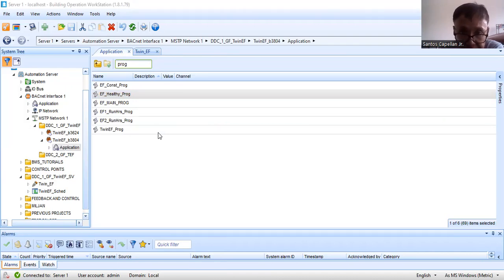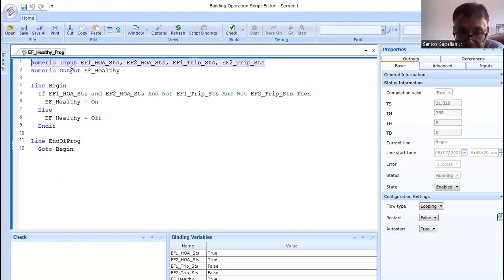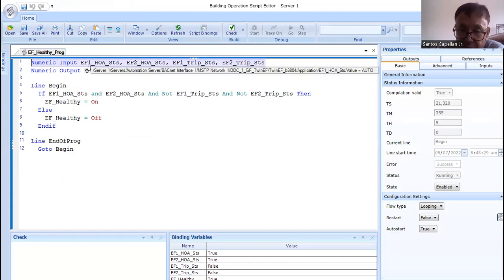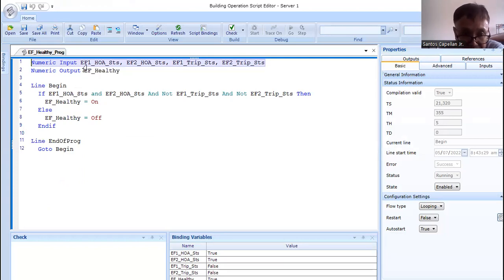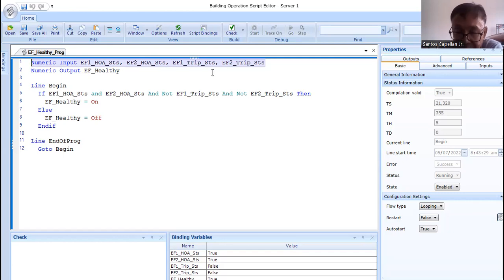I will share this screen so you can see it. This is a very small program. I have the first lines as numeric input. These numeric inputs are the points I will get from the controller. First: EF1 hand-off auto status — very important. EF2 hand-off auto status. EF1 trips and EF2 trips. My system will not be healthy if one or both of the fan selector switches are in manual or off, meaning I don't have any ready exhaust fan to serve the area.